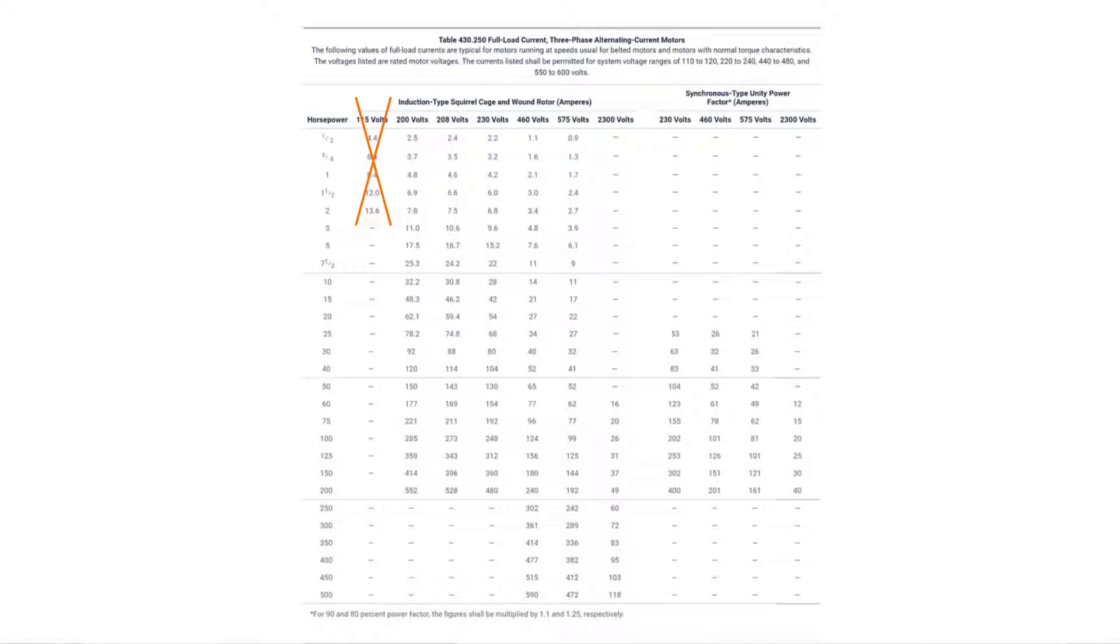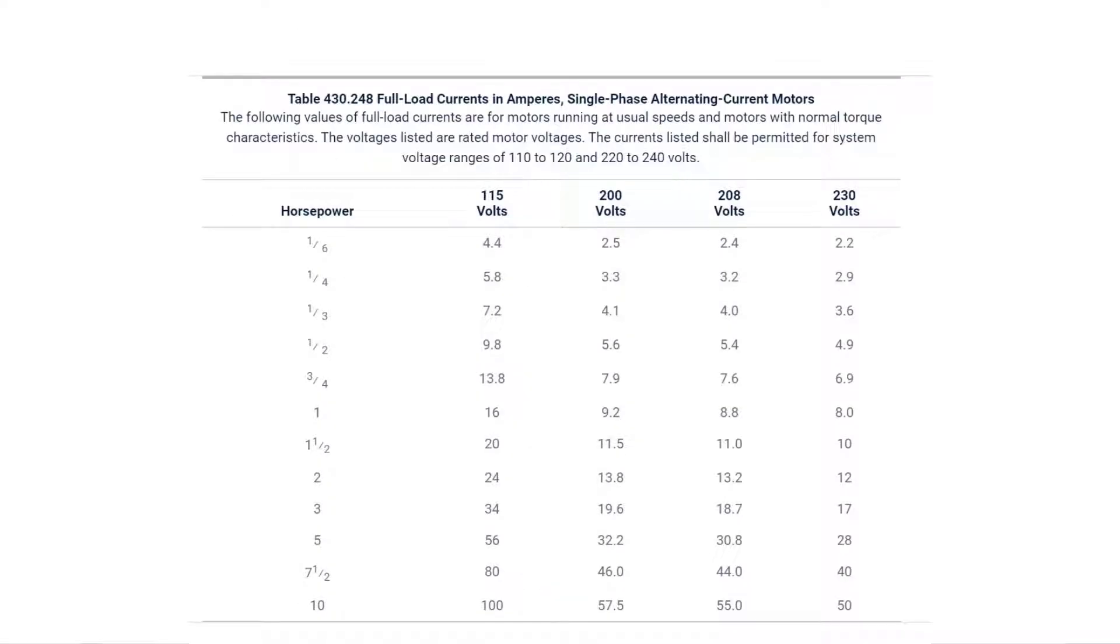And then I want you to look at the voltage ranges from left to right. Between the 460 and 575, I want you to do what I call a fence post. Straight line between to the right of the 460 voltage and to the left of 575, straight down. Make a line with your dark color highlighter. At the very top of this page where it says 430.250, I want you to write three-phase. That way you know this table is for three-phase. Over top of the 430.248 table, I want you to write single-phase. The 248 table is all about single-phase.